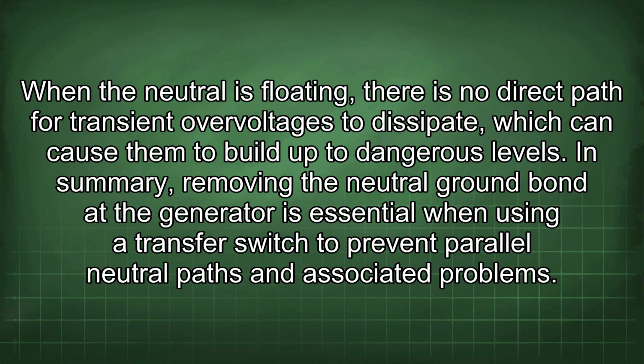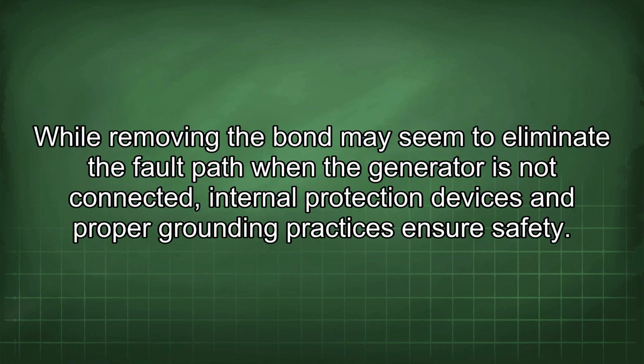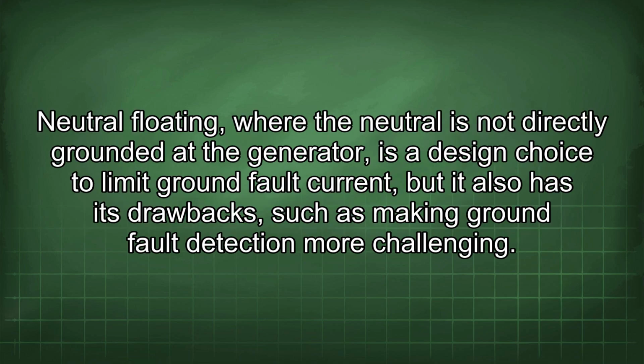In summary, removing the neutral ground bond at the generator is essential when using a transfer switch to prevent parallel neutral paths and associated problems. While removing the bond may seem to eliminate the fault path when the generator is not connected, internal protection devices and proper grounding practices ensure safety. Neutral floating, where the neutral is not directly grounded at the generator, is a design choice to limit ground fault current, but it also has its drawbacks, such as making ground fault detection more challenging.